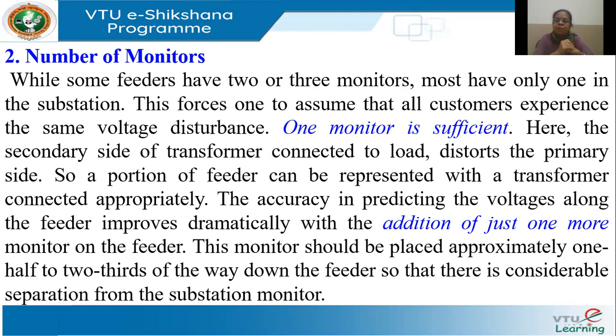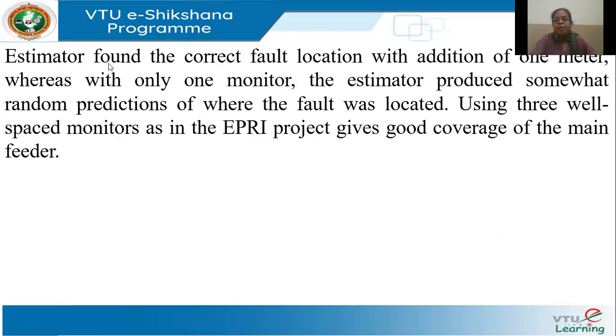If I put one more monitor on the secondary side of the transformer, experience tells that this will improve the estimation. So where should it be located? Approximately, the studies reveal that it should be located at half or two-thirds of the way along the feeder after the secondary of the transformer. That means I have one monitor at the substation and another along the feeder, halfway. There is considerable distance between the two monitors. This has been found to improve the accuracy. With the estimator which EPRI developed, it was found that with the addition of just one more meter, the fault location could be identified correctly.